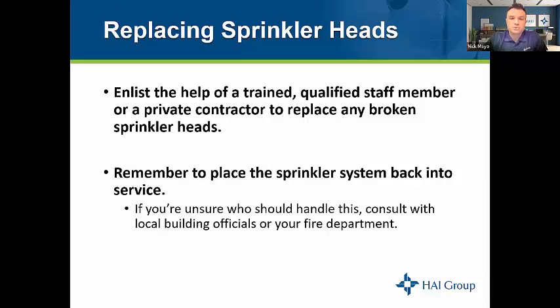If we have to replace a sprinkler head within our building due to an activation, whether from a fire or an accident, we want to enlist trained, qualified staff members or private contractors to replace any broken sprinkler heads. We need to have a particular number of sprinkler heads in reserve, typically kept in the fire protection room. The total number of sprinkler heads in a building will determine how many we need to have in reserves.